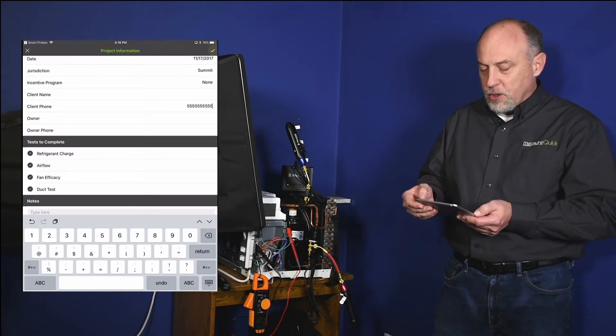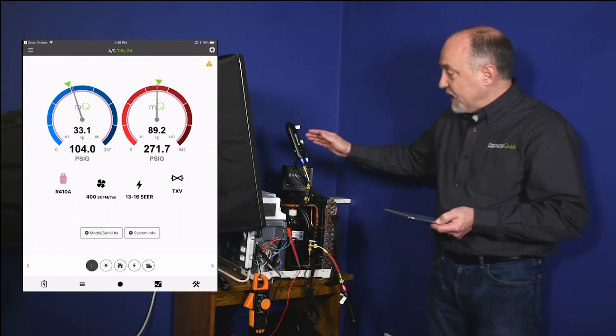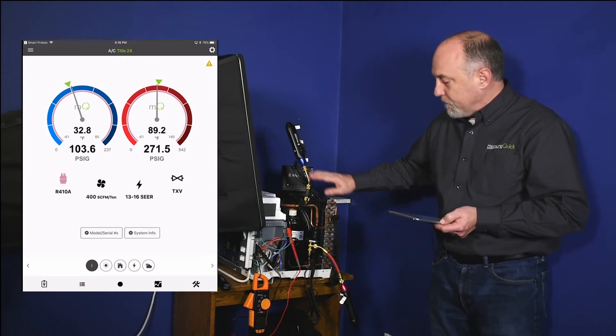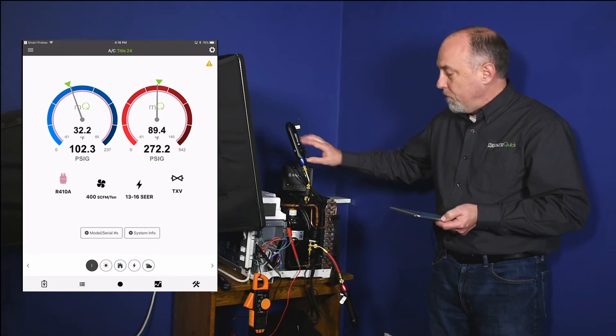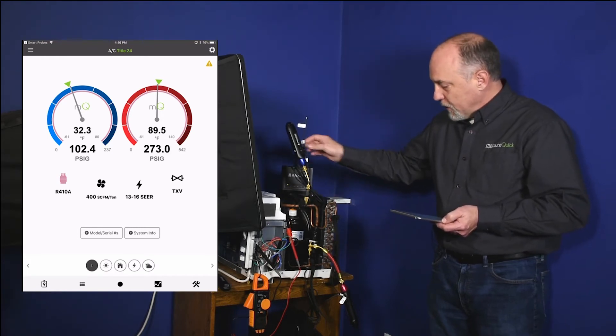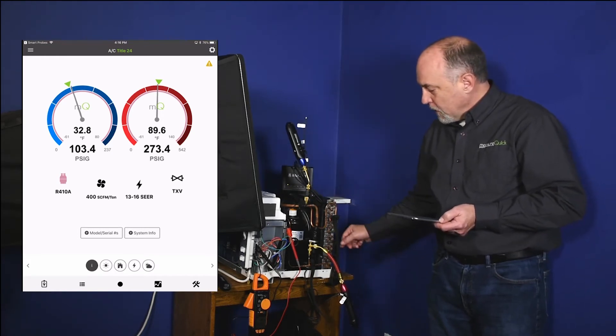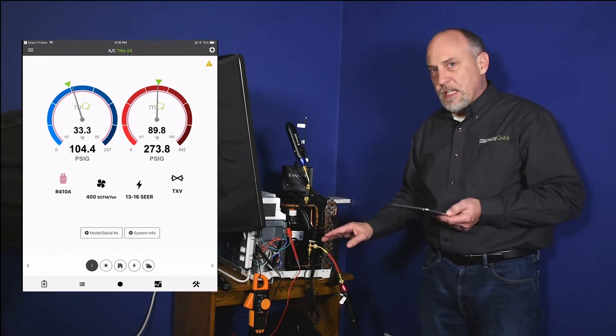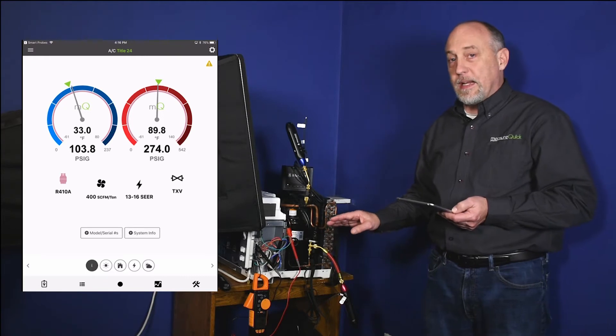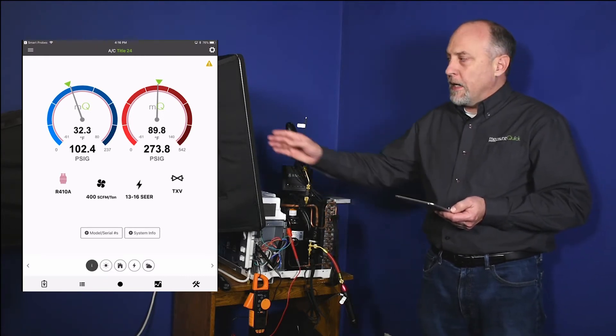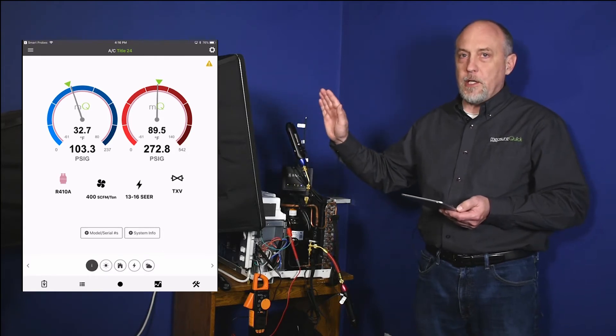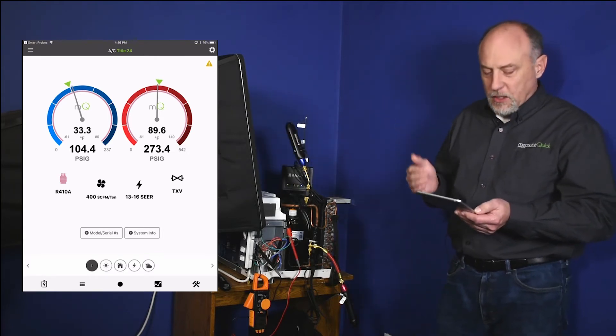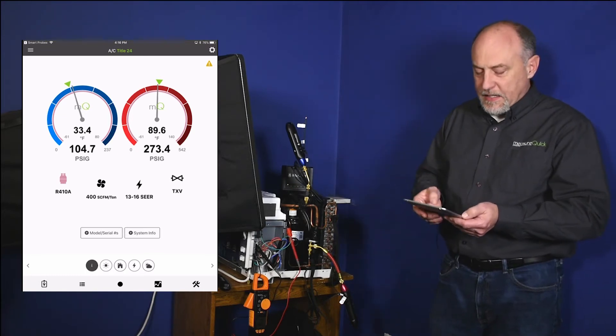So now you can see I've got an iConnect sitting here. I've got all the probes hooked up. So I'm ready to do my refrigerant charge testing. I've got a low pressure probe, suction line temperature, this is my outdoor air temperature. I've got a high pressure probe, liquid line and discharge line temperature. And down at the bottom here I have a Testo 770-3 watt meter. So I can get my watts of my condenser and I can get my fan watt draw. And then I've got a 420 capture hood here. And the capture hood is going to be used to pull the data in for the airflow readings on this thing. So we're going to make this, I'm going to show you how easy this thing is to do.